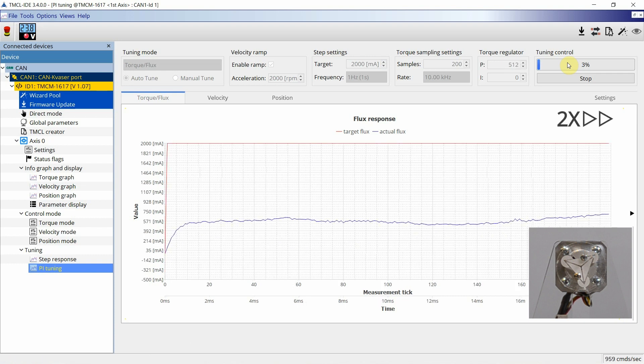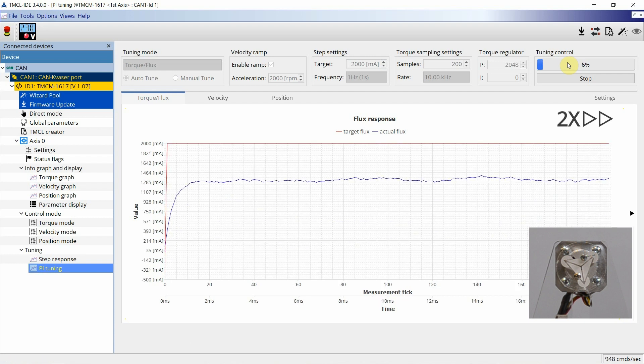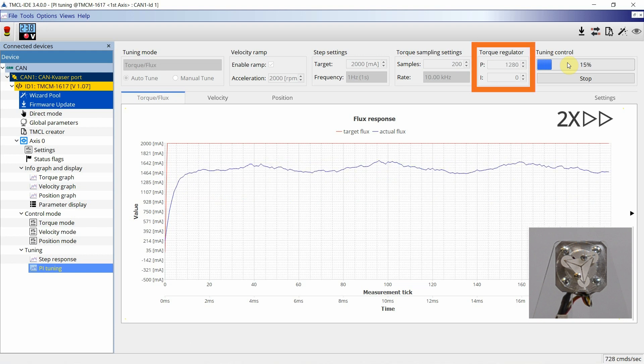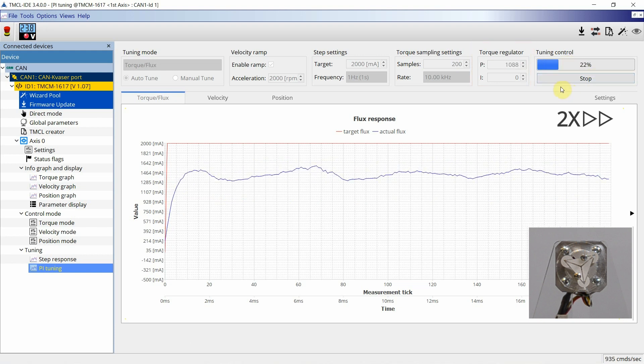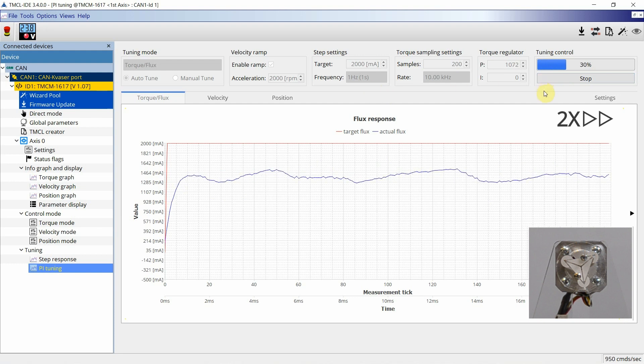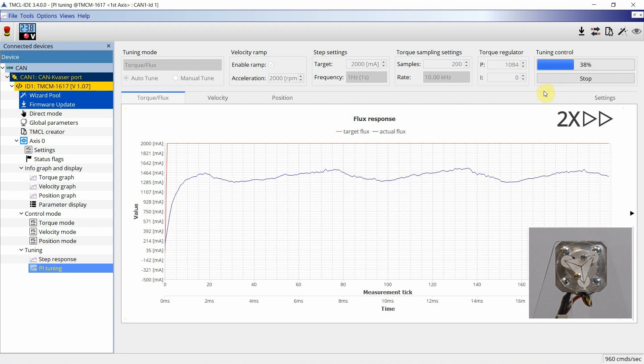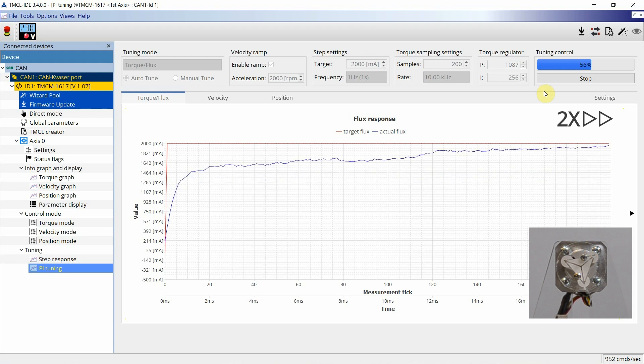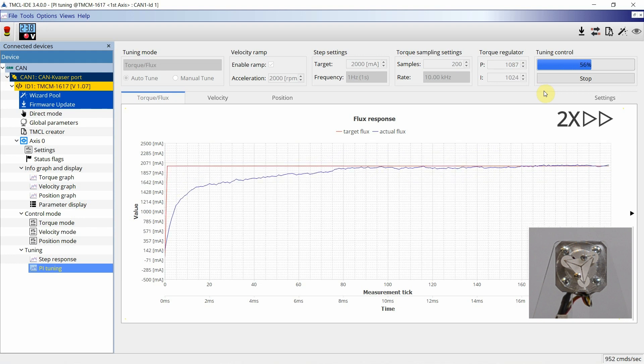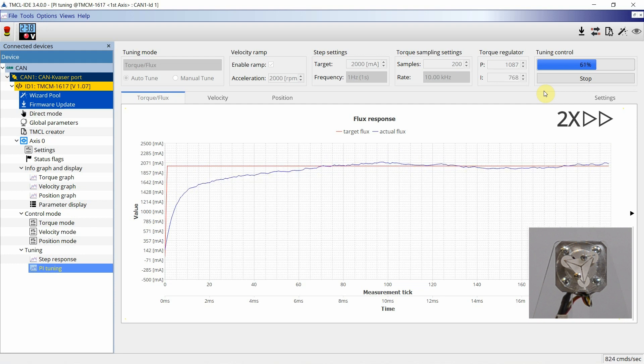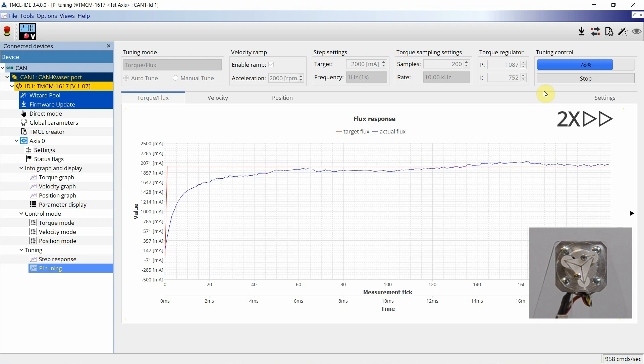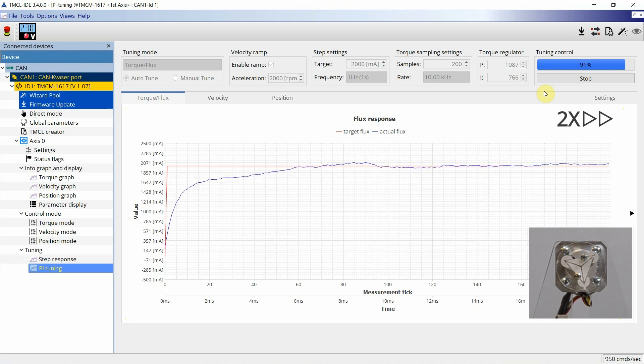During the tuning, current step responses are automatically applied and the PI parameters are adapted. The resulting current is displayed and constantly updated. As only flux current is applied, the motor is not moving during the step. After suitable PI values with minimum error have been determined, the auto-tuning process for the current loop is finished.